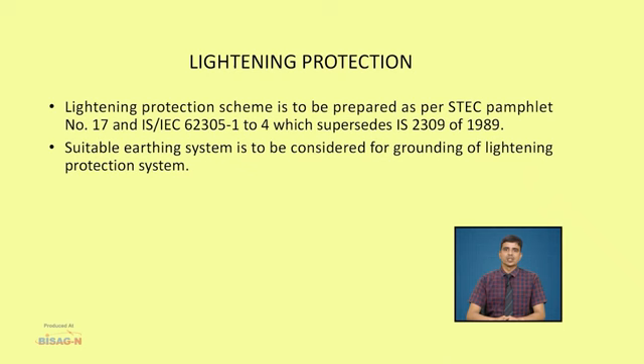Now I will talk about lightning protection. The lightning protection scheme is to be prepared as per STEC pamphlet number 17 and the relevant IS code or IEC 62305-1 to 4, which supersedes IS 2309 of 1989. A suitable earthing system is to be considered for grounding of the lightning protection system.